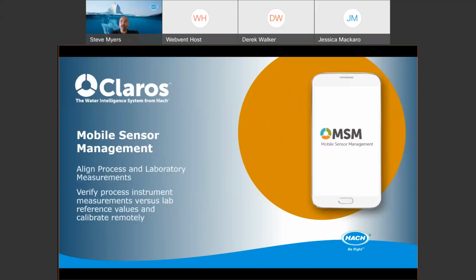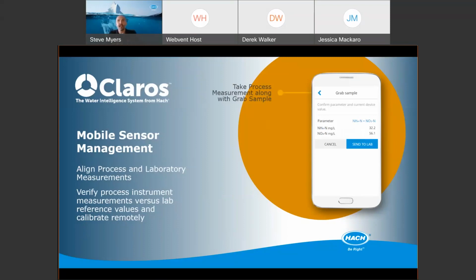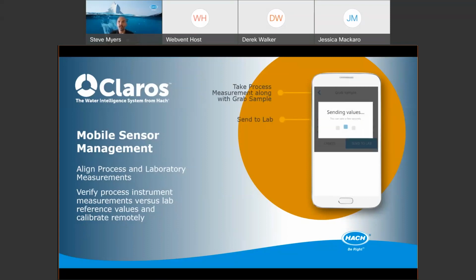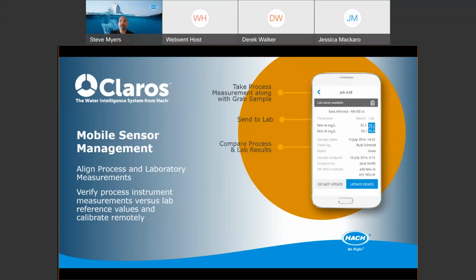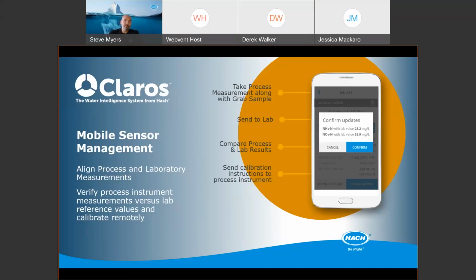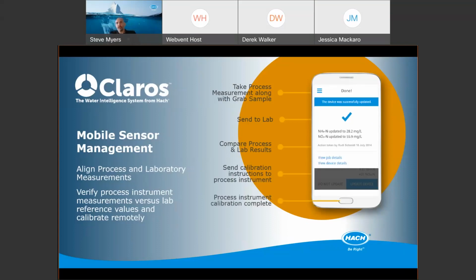In addition to this, complementing the laboratory discussion we've had before, a lot of these online instruments do require some level of calibration or validation to keep the accuracy up. And with the mobile sensor management, we can link the lab with the process highly efficiently by, for example, taking a grab sample at the same time as you're doing a measurement validation, and you can send to the lab the measurement from the online device while you're taking the grab sample to the lab. And as soon as the lab is able to process that lab measurement, you can compare and contrast what the measurements are between the lab and the online instrument, and in many cases upload a calibration to the instrument based on the laboratory reading. So this helps streamline the SOP for those specific online instruments, and essentially keeps a log of when and how often this is done, and tries to make this as easy and streamlined as possible.